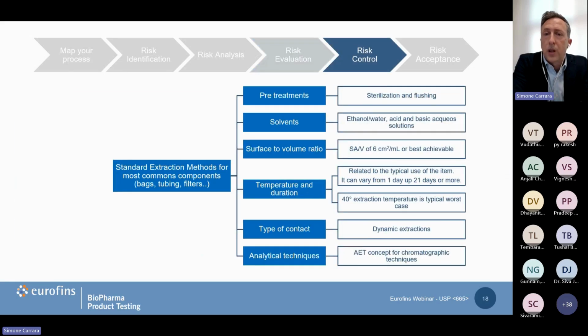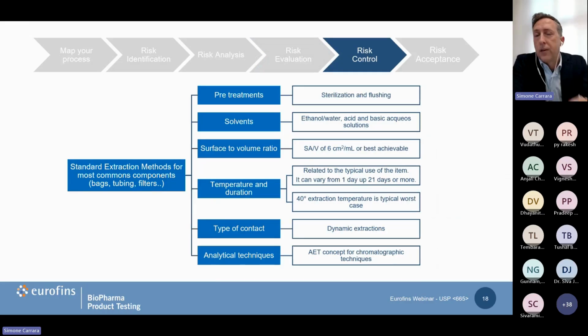Moving forward in our risk assessment, we reach the situation of risk control. Risk control means we need to perform the extractable study on our item, pre-treated as it would be in real conditions. So if it is sterilized and flushed, then we need to test the item in that situation.